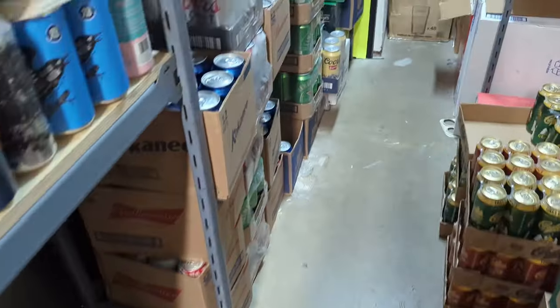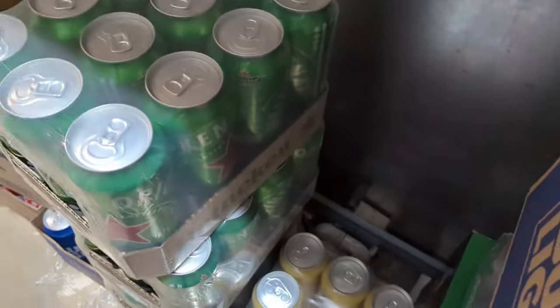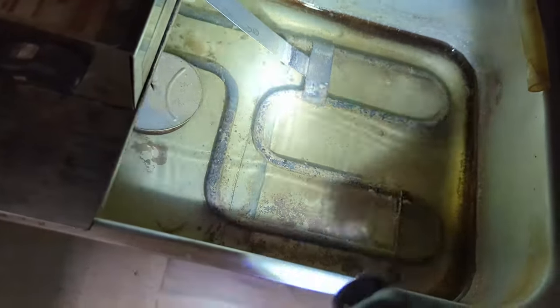Which is cool because now I've checked on the condensate pumps as well. Now I know that digital controller is working defrost-wise properly. Remember these condensate pumps from a couple weeks ago? They're now nice and wet. They were bone dry before. And look at all this beautiful condensate. That's a good amount. Yes, it's working.